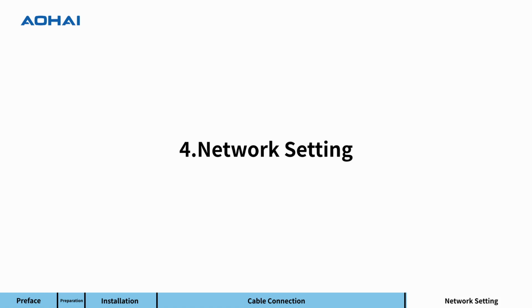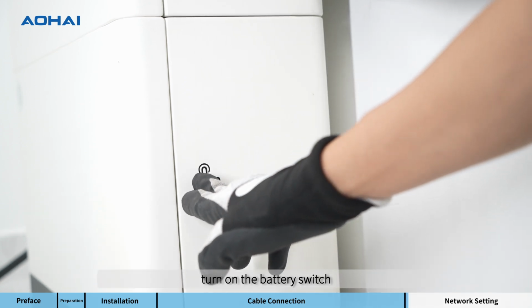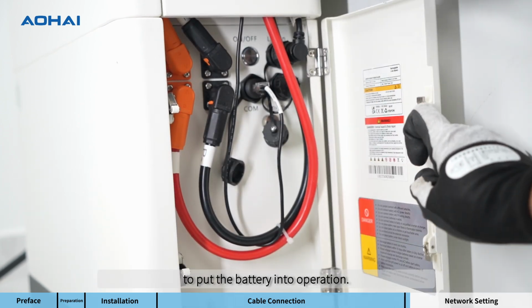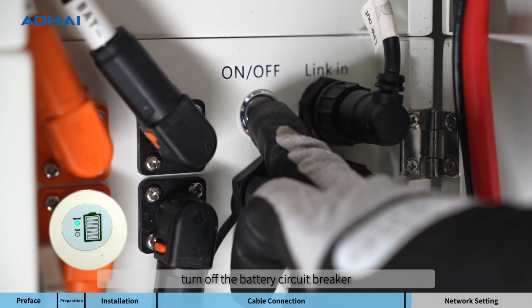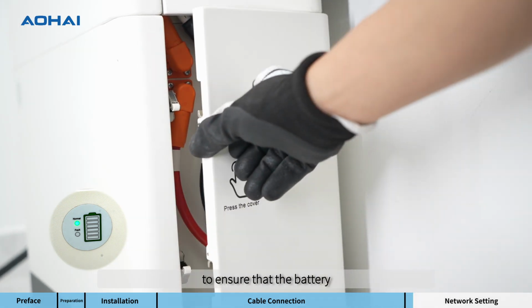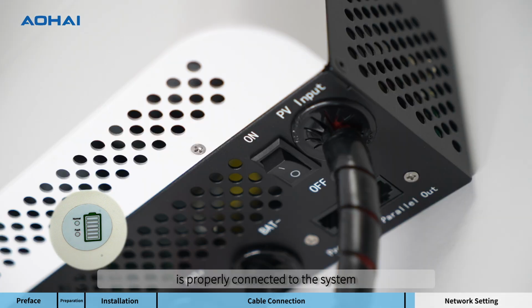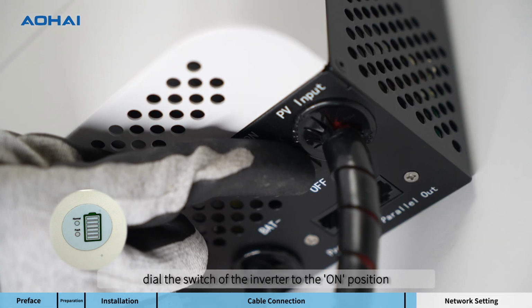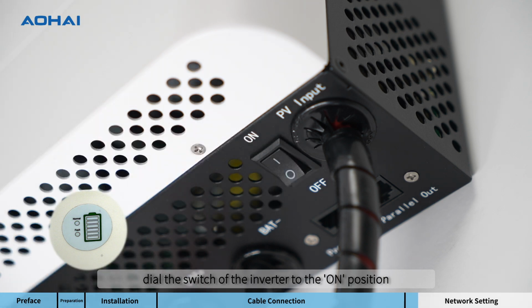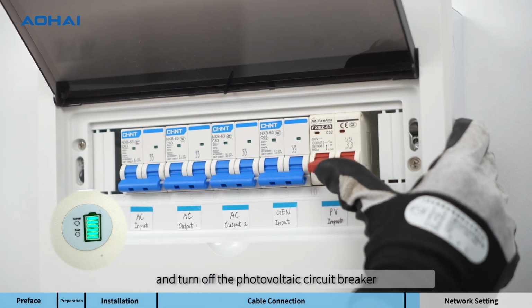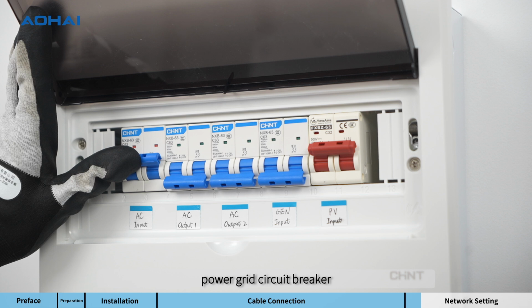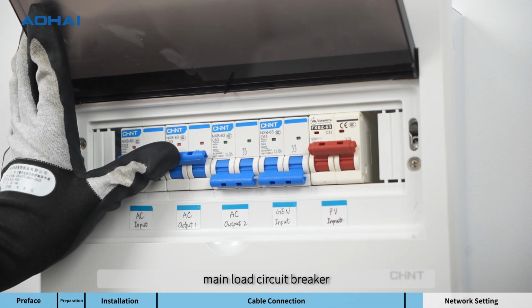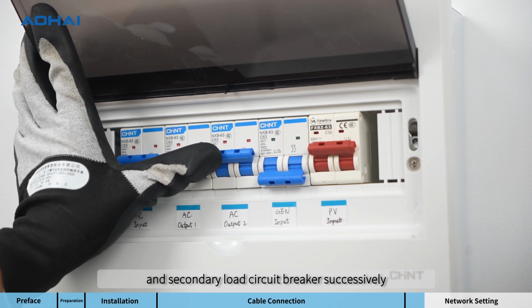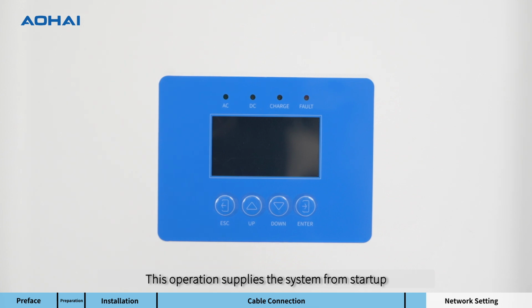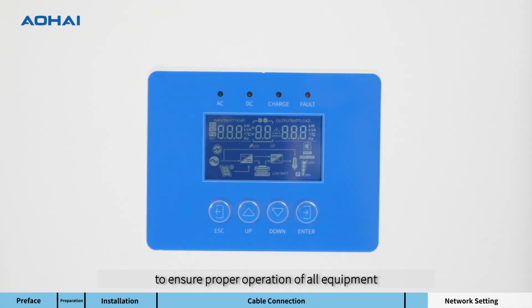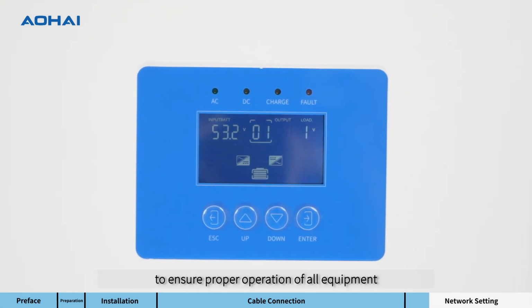Network setting. First, turn on the battery switch to put the battery into operation. Then, turn on the battery circuit breaker to ensure that the battery is properly connected to the system. Next, turn the inverter switch to the on position and turn on the photovoltaic circuit breaker, grid circuit breaker, main load circuit breaker and secondary load circuit breaker successively. This operation starts up the system to ensure proper operation of all equipment.